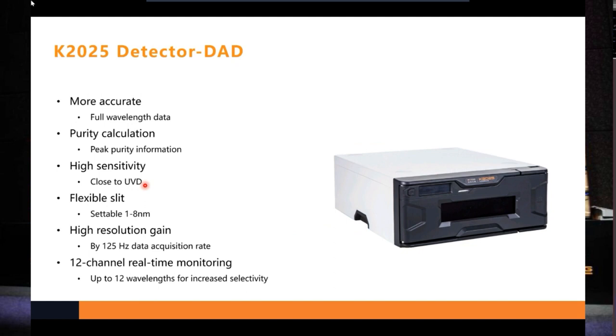DAD can be treated as an upgrade version of UV detector. More information can be acquired because the samples are to be scanned with full wavelengths. And this is why DAD can calculate the purity of a specific peak. For sensitivity, DAD actually is a bit lower than UVD. But it has a flexible slit, so we can set the bandwidth for high resolution mode or high throughput mode. And the sampling rate can reach 125 Hz and up to 12 channels.